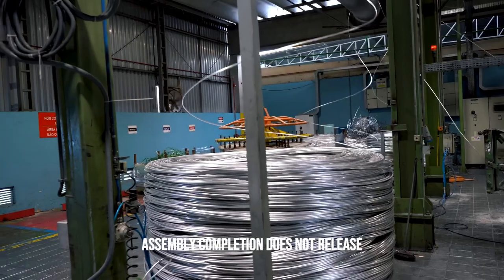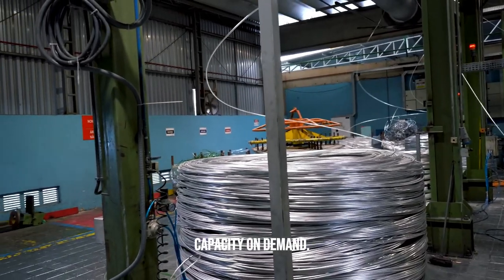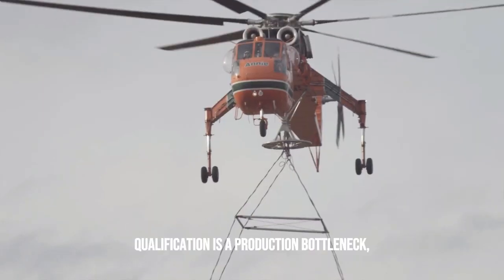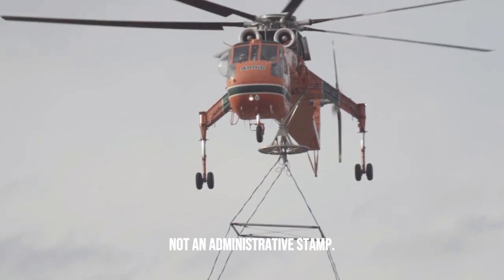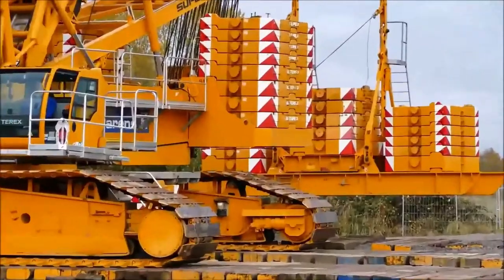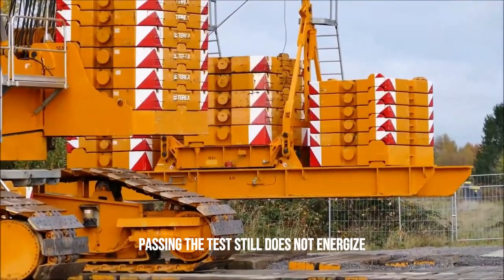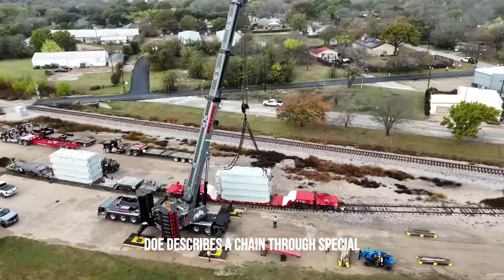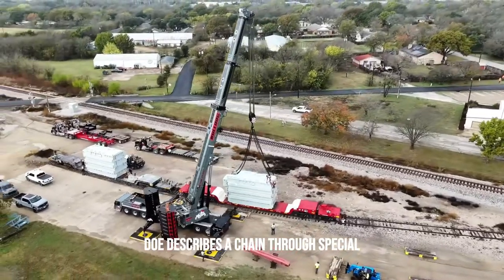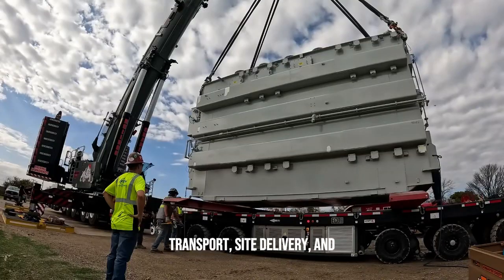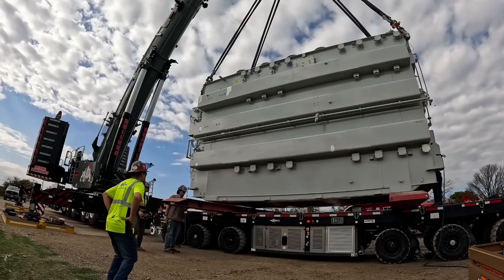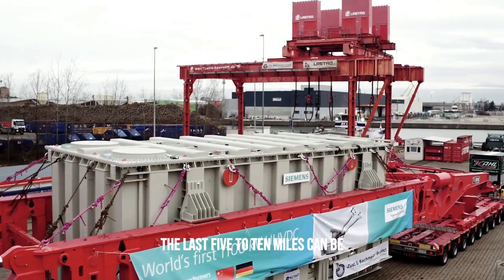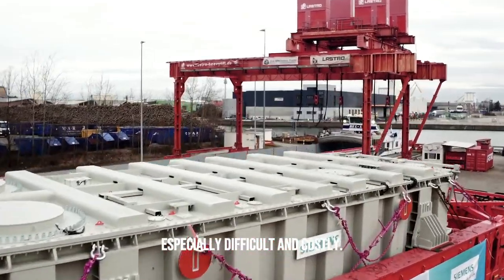Assembly completion does not release capacity on demand. Qualification is a production bottleneck, not an administrative stamp. Passing the test still does not energize the machine. DOE describes a chain through special transport, site delivery, and installation. The last 5 to 10 miles can be especially difficult and costly.